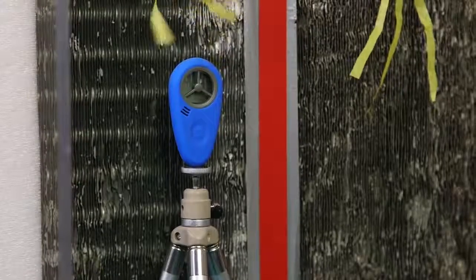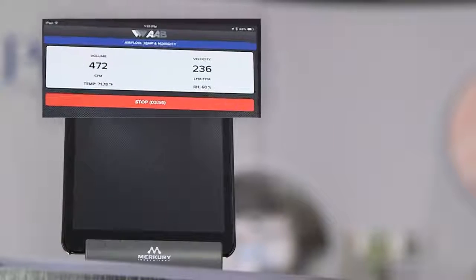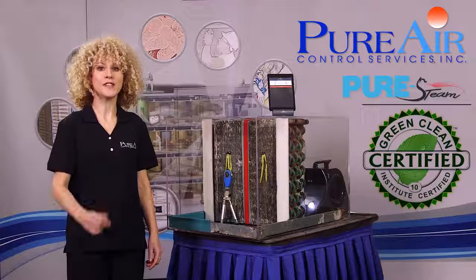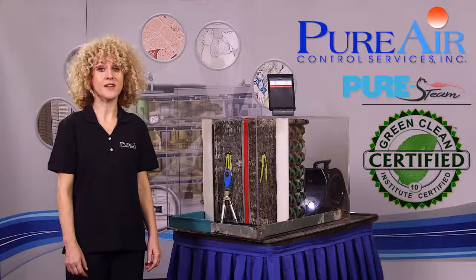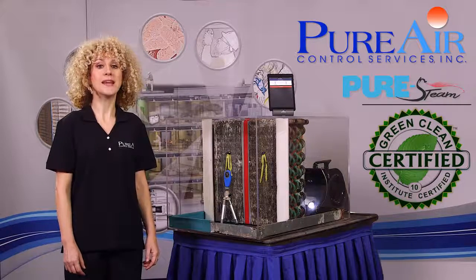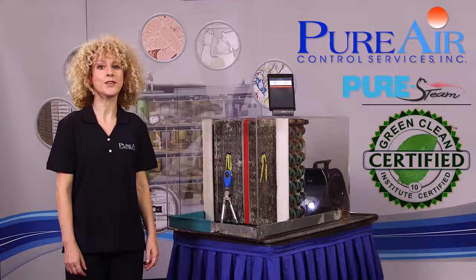On the left side of the coil, Pure-Steam coil cleaning was utilized. As you can see, the airflow is much improved to the tune of over 400 CFMs — a remarkable difference. Imagine the benefits for your facility of energy cost savings, reduced risk of airborne infections, and a cooling and heating system that actually works the way it was designed.